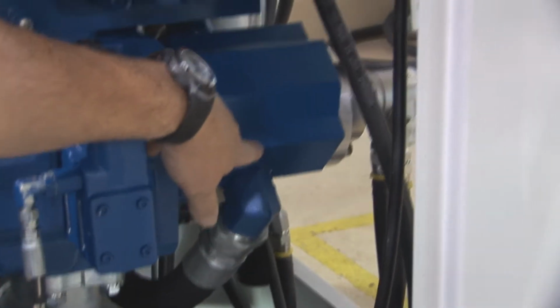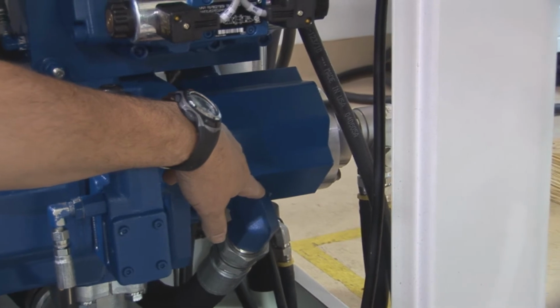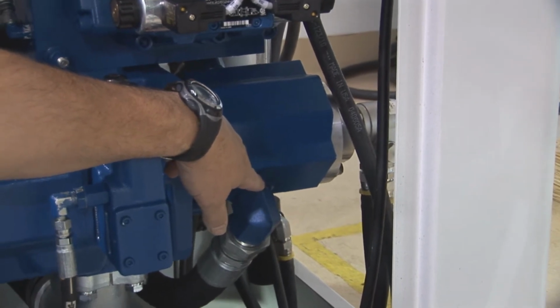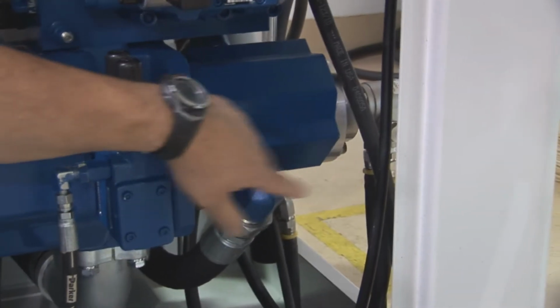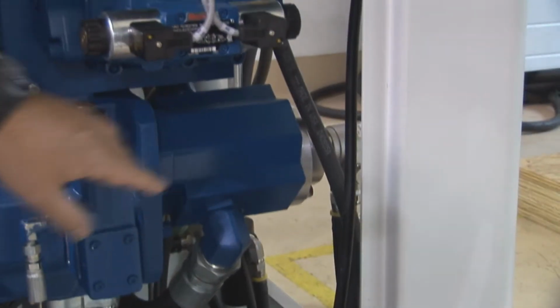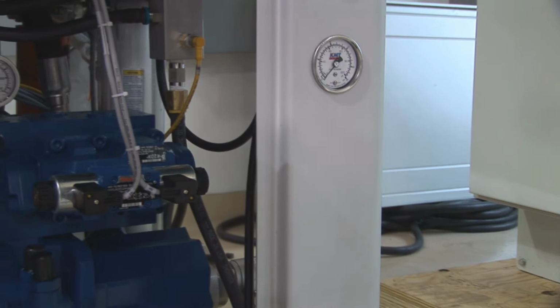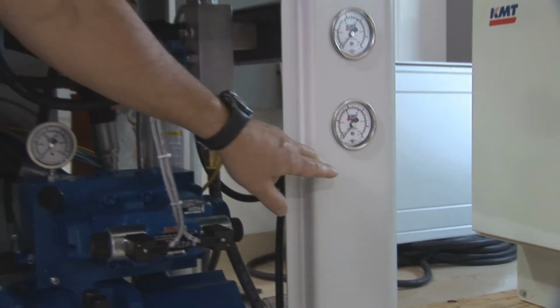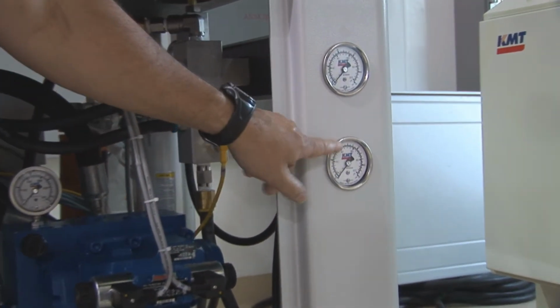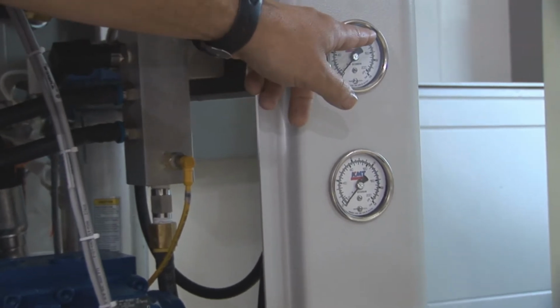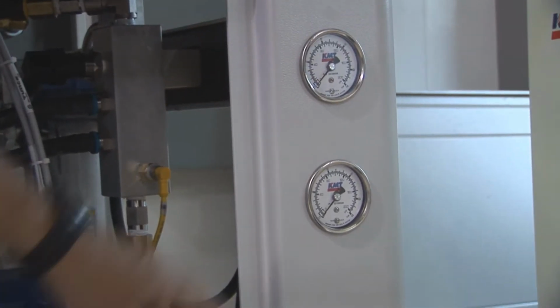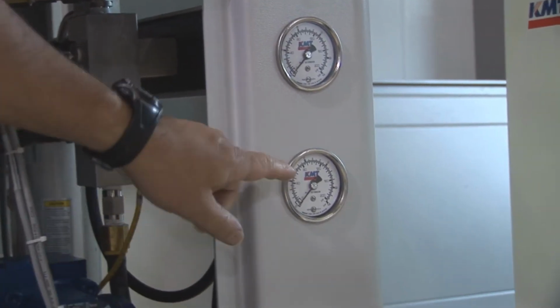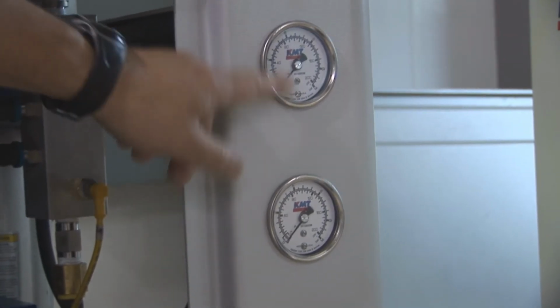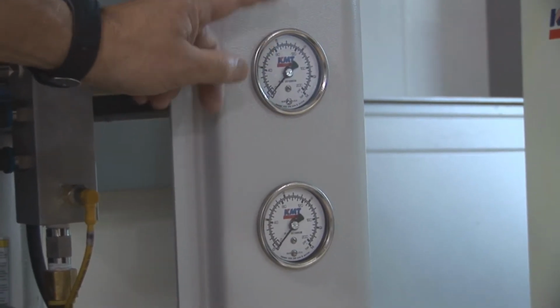The other pump we have is a recirculation pump. It produces the cooling of the oil and filtering of the oil through the heat exchanger and back through the filter. The other pump we have is the booster pump. It takes your city water pressure from 30 to 40 psi up to 120 psi. There's a pressure switch that shuts the machine down if it gets below 30, and there's a pressure switch that gets below 60, it will shut the machine down.